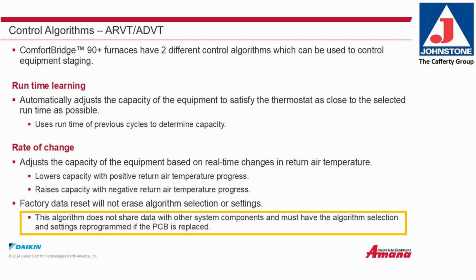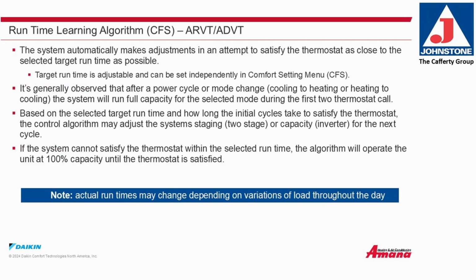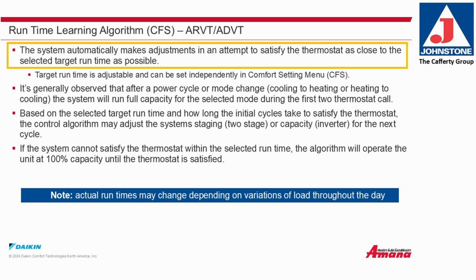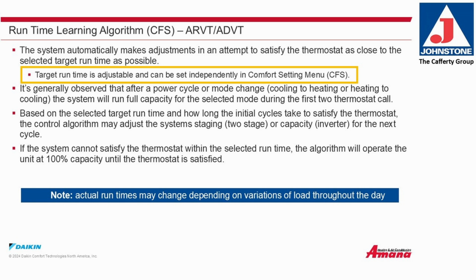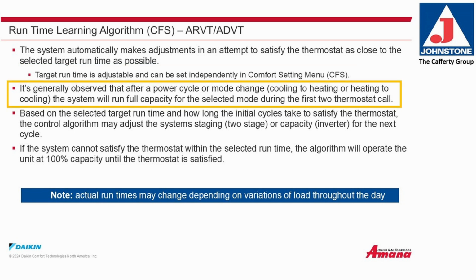Runtime learning algorithm, communicating system. The system automatically makes adjustments in an attempt to satisfy the thermostat as close to the selected target runtime as possible. Target runtime is adjustable and can be set independently in Comfort Settings menu, CFS. It is generally observed that after a power cycle or mode change, cooling to heating or heating to cooling, the system will run full capacity for the selected mode during the first 2 thermostat calls.